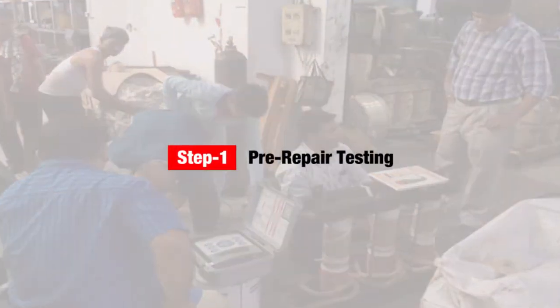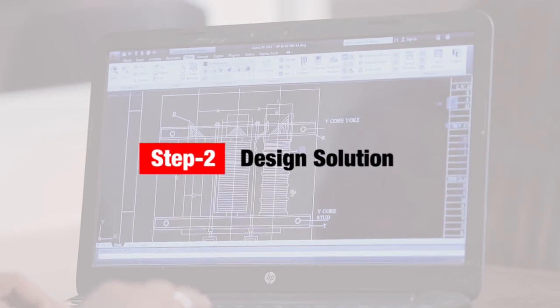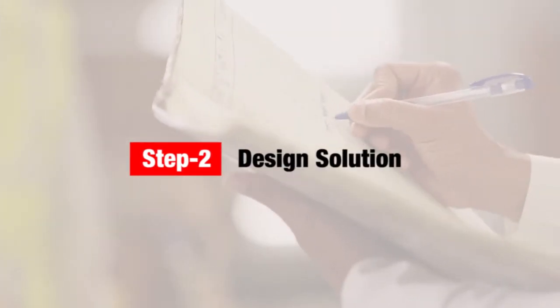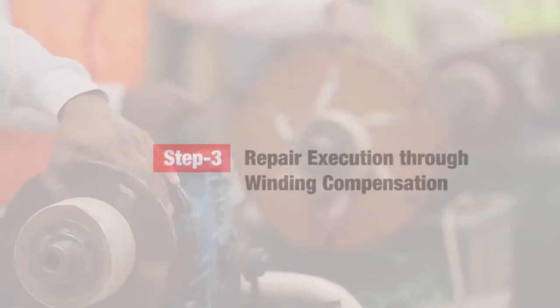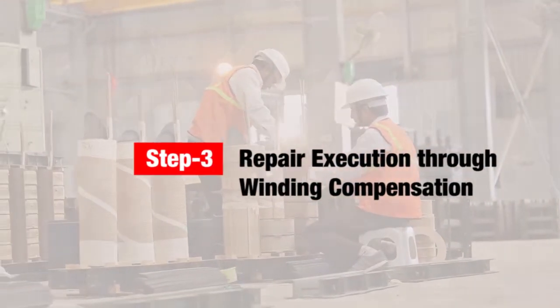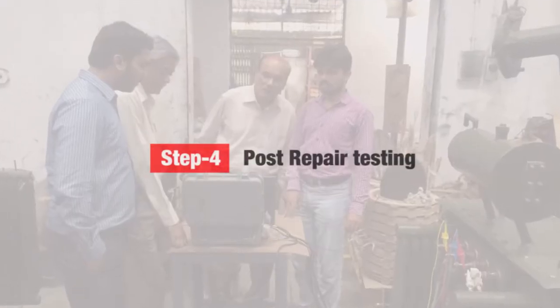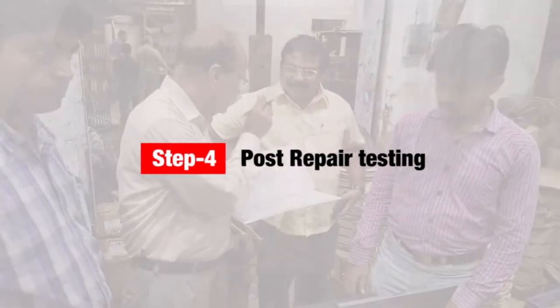How we did? Active Repair Solution focuses on technical loss reduction in DTs through winding compensation, including any change in winding material. The core, if not beyond a certain level of degradation, is left unchanged as different makes of DTs will require different laminate designs and cuts, and that would not be an easy and replicable repair methodology.